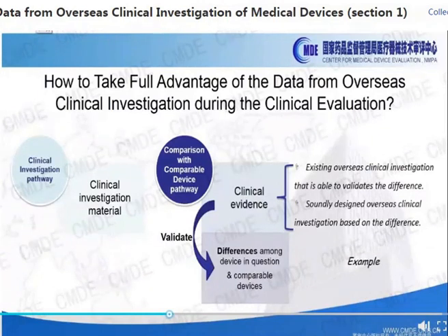When applicants plan to extend the use of an implantable cardiac pacemaker in the MRI environment, overseas clinical investigation can be submitted to confirm the safety and effectiveness of the device used in the MRI under labeled use. Of course, based on the technical innovation compared with the older generations, other clinical data may also be required, such as the published literature, reports of clinical experience, post-market reports, and adverse event data.